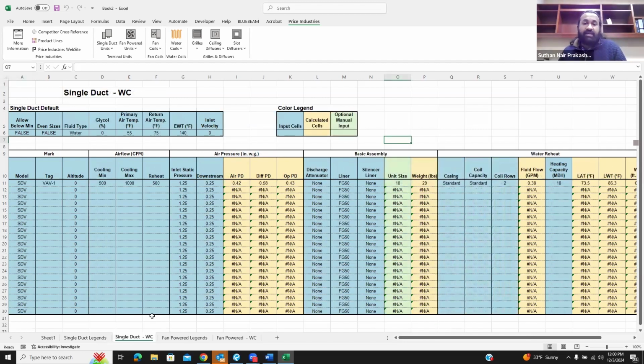So they would calculate everything on a theoretical basis. They have their preset equations that they use to get the heating load and so on. So if they have it in Excel, I would just copy and paste the cooling min, cooling max, the reheat and all the rest, and they can get a dynamic performance, which is very close to their theoretical performance, but closer to what our practical, priced VAV box performs at that particular point. So they're going to port over their tag, cooling max, reheat, and probably MBH, depending on what their solution method is.